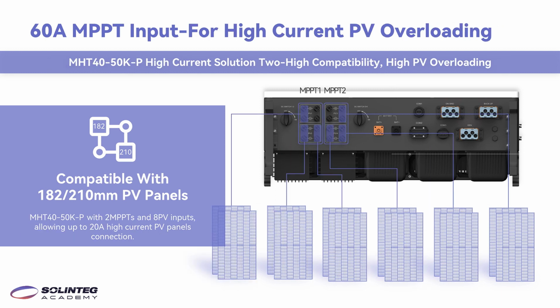On this page, you can see another version, the 40 and 50 kilowatt inverter. They have only 2 MPPT, and for each MPPT, there are 4 PV inputs. So the MPPT current is 60 ampere. If you connect with the 210 millimeter PV panels, you can connect 3 PV strings with each MPPT. So in total 6 PV strings you can connect with one inverter.